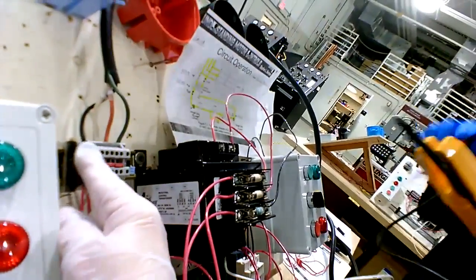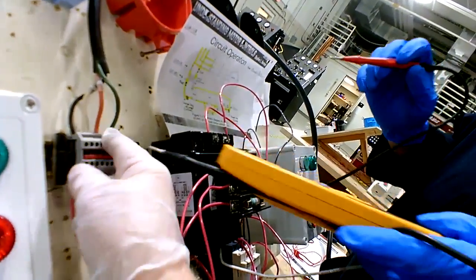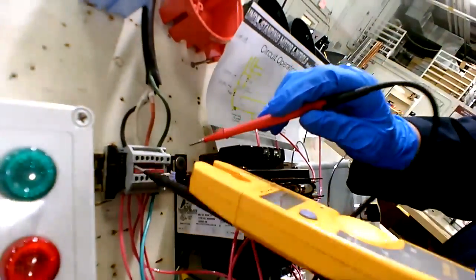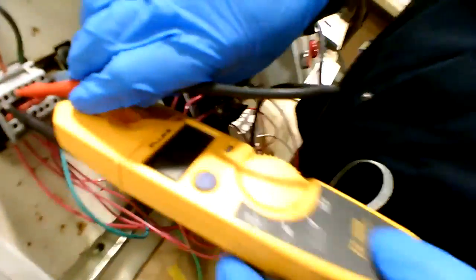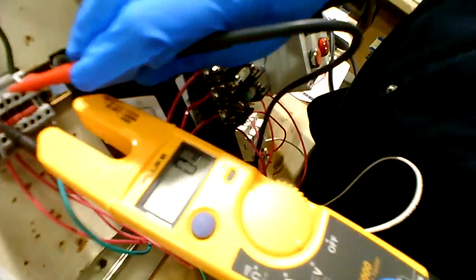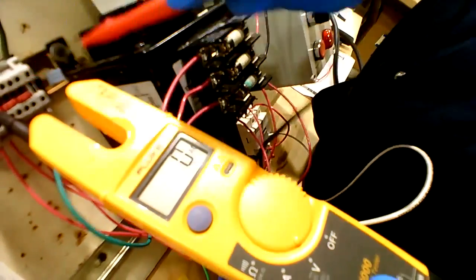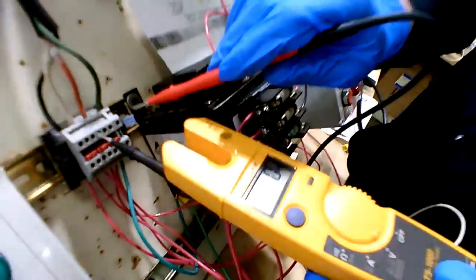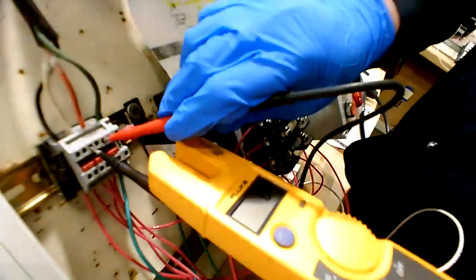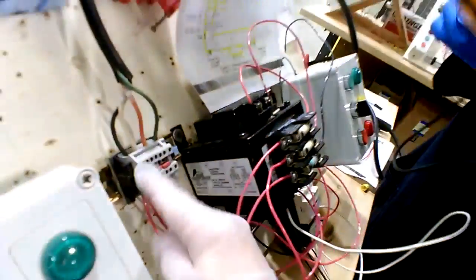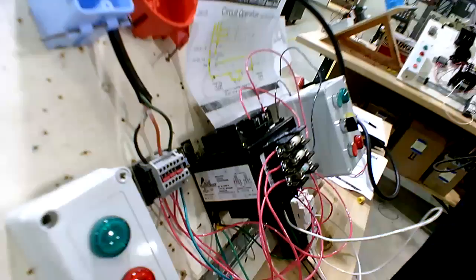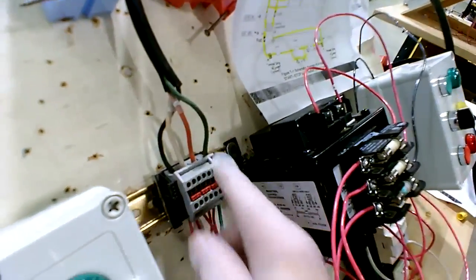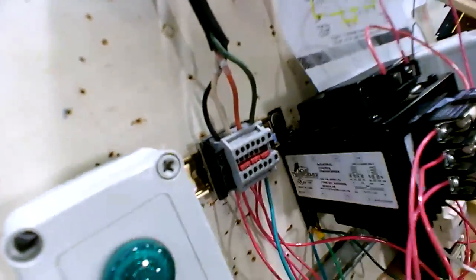Now go phase to phase, from L1 to 2, 1 to 3, and then 2 to 3. So that's called phase to phase. In this case, you've got 208 coming in. It's not even 230, 240, it's 208 in this one. So leg to leg or phase to phase is 208 in those three combinations, and the leg to ground will be 120. You'll find that when we cut it back on.